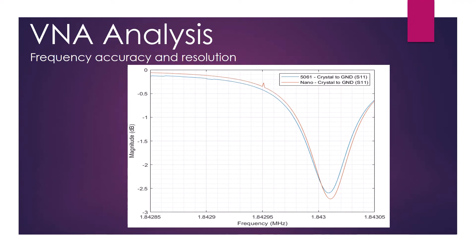Narrow bandwidth devices such as a crystal oscillator are very common in microwave circuits, so we would like to have a device that can measure the performance of these crystals. This graph shows a 200 Hz bandwidth with 200 discrete frequency points, meaning each of the VNAs is stepping 1 Hz at a time. This is very good frequency resolution.